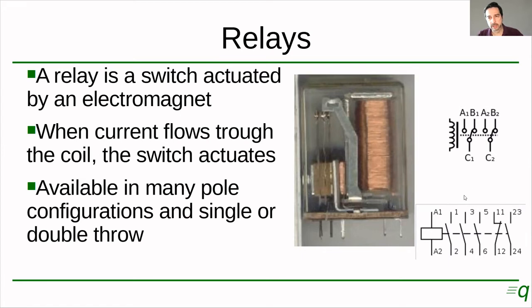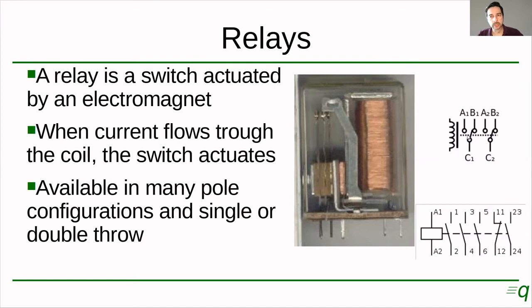This is the symbol, and this is another symbol — you will see either of these two. There are other options which are different variants. What you see here is a double pole, double throw switch. If you remember from our second class, we studied this. The dotted line means that the two switches are connected together mechanically, and this dotted line also extends to the coil, meaning that the coil is actually controlling the switch. So when current flows through the coil, these switches are going to move to the left, to A1 — it's going to connect C1 to A1 and it's going to connect C2 to A2.